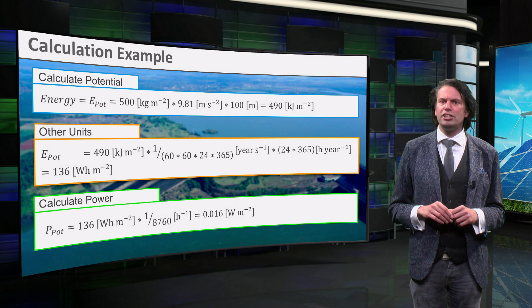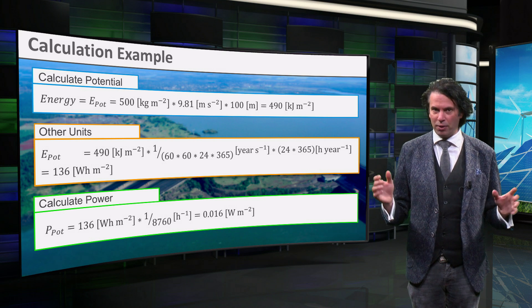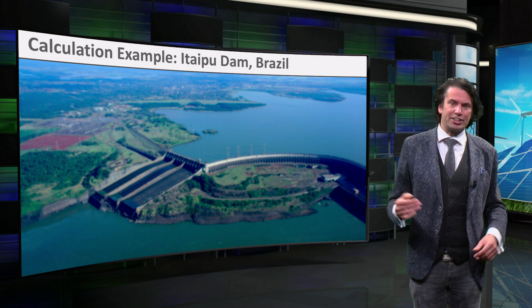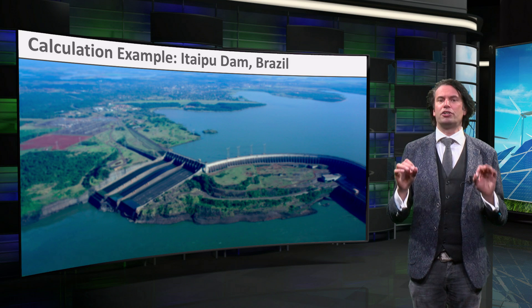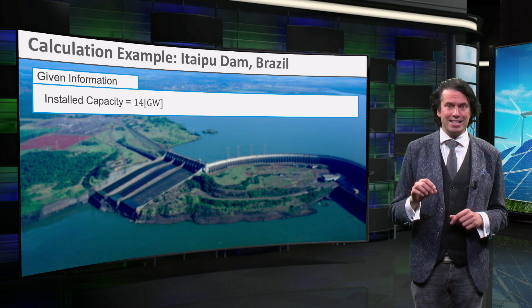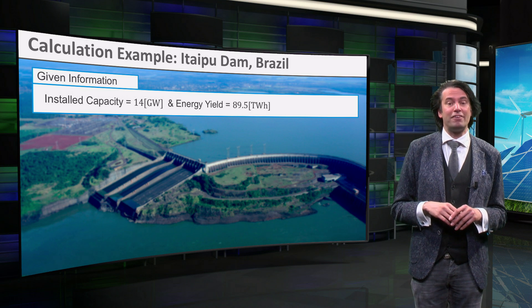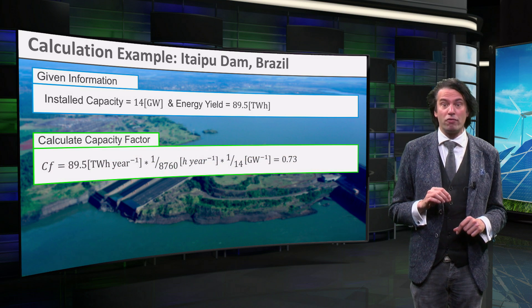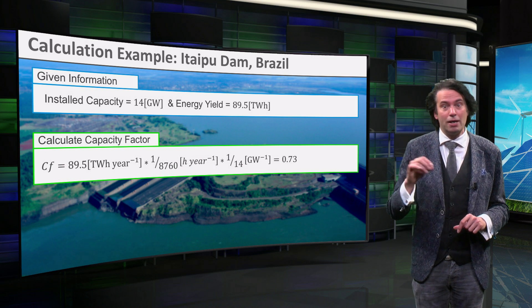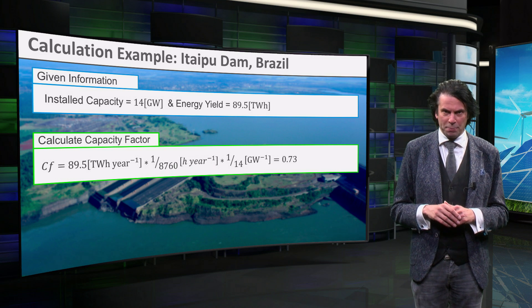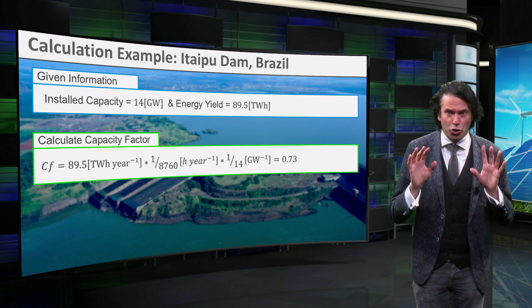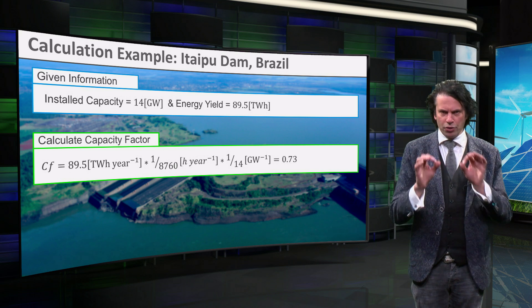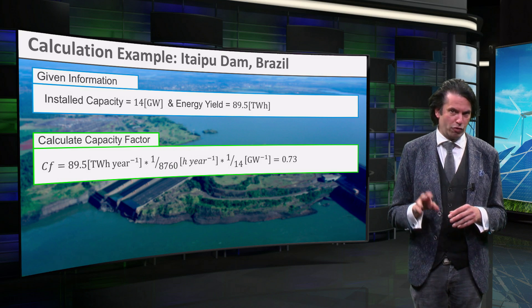To learn more about the total energy yield, let's take a closer look at the Itaipu dam on the border of Brazil and Paraguay. The Itaipu dam is the second largest hydropower plant on the planet. It has a total installed generation capacity of 14 GW and, in 2015, reached a yield of 89.5 TWh per year. Using these values, we can calculate the capacity factor. If we divide 89.5 TWh by 14 GW times the total hours in a year, we receive a capacity factor of 0.73. So on average, the dam produces electricity at maximum capacity during 73% of the time. Note this value is much higher than the average global capacity factor for hydropower of 0.40.